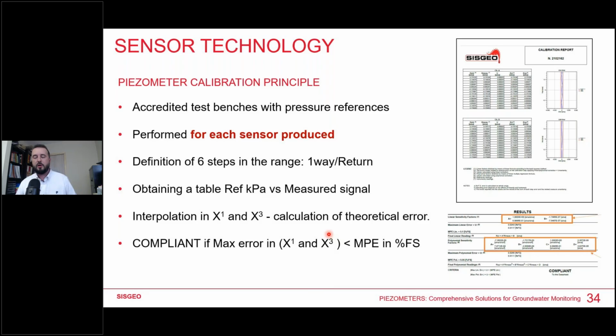So how does it work? We put the sensor on a bench, connected to a reference pressure sensor, and we define 6 steps from 0 to the full scale. We raise the pressure and measure the signal, and go back to 0. Then we obtain a table. In this table, we compare the reference pressure given from the bench to the measured signal. We make an interpolation, linear and polynomial, and then we calculate the theoretical error from it.